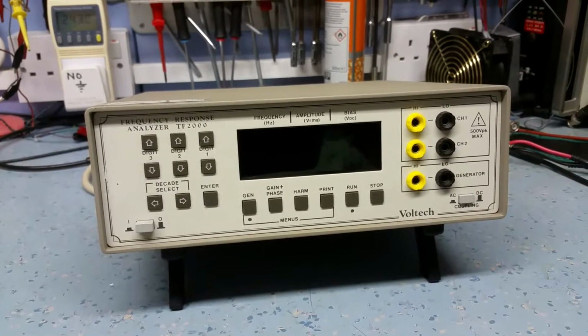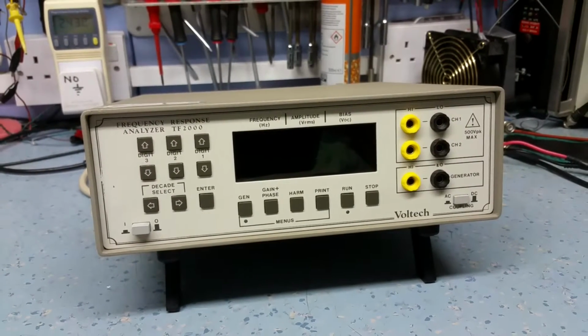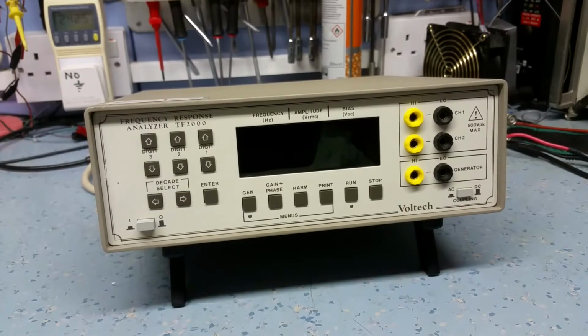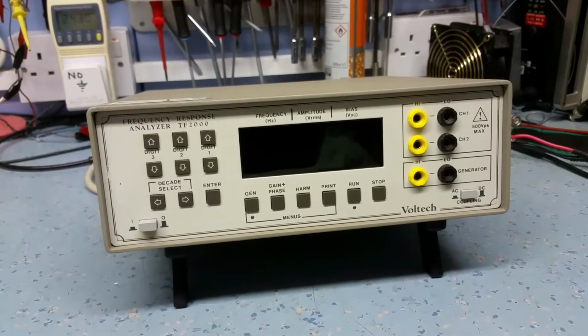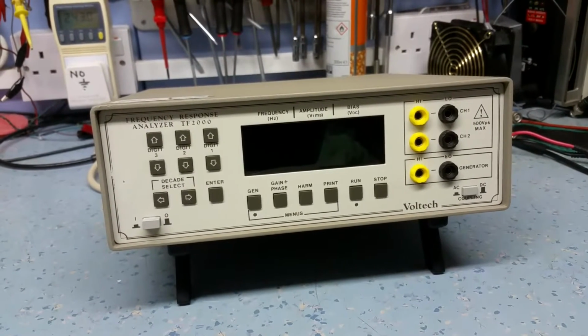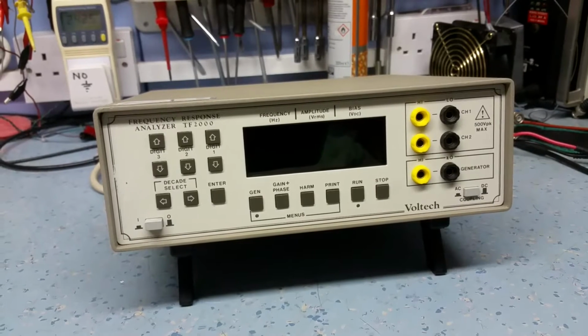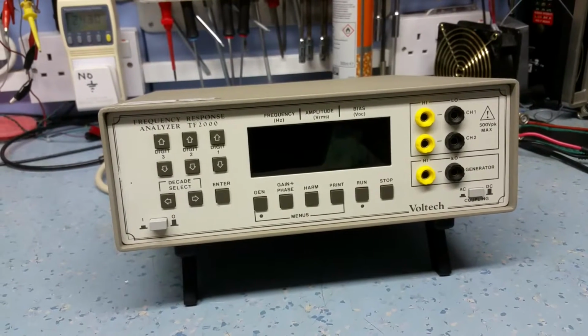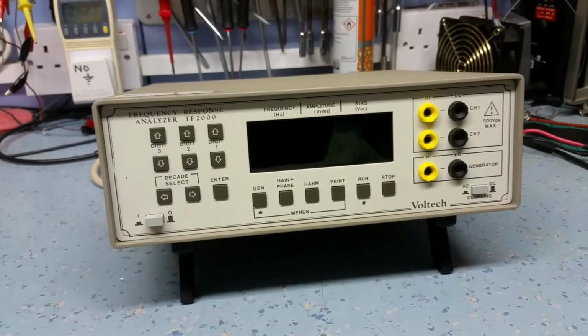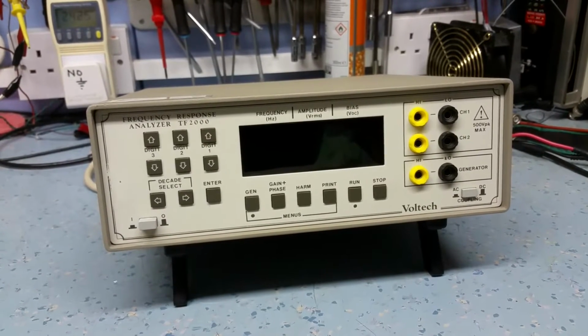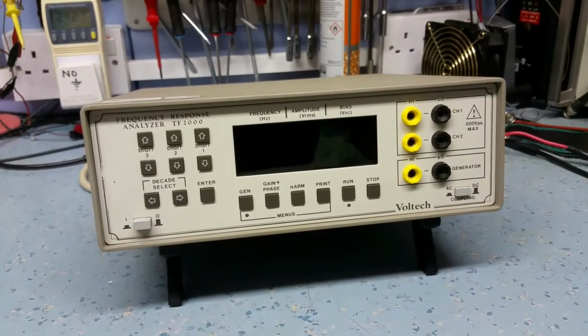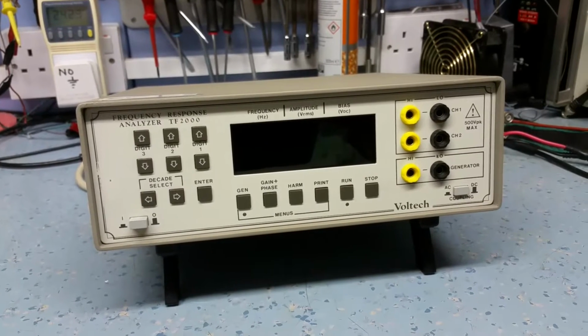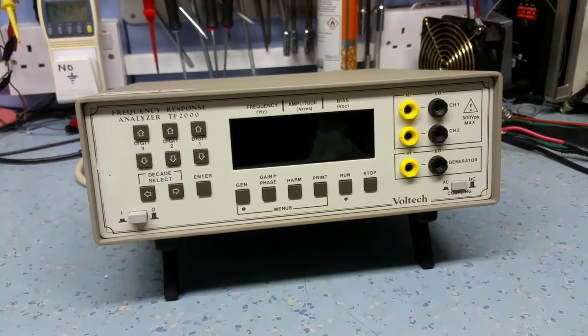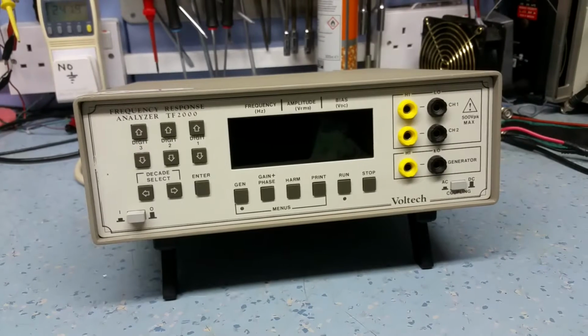I immediately thought I know what's, well, I think I know what's wrong with it, should I say. When the description came through, it sounded to me like the typical sound and smell of a burnt out capacitor on the front end of the inputs. You know, the IEC X capacitors that are designed to filter out noise. Well, these capacitors fail with age, as they do on quite a lot of equipment.